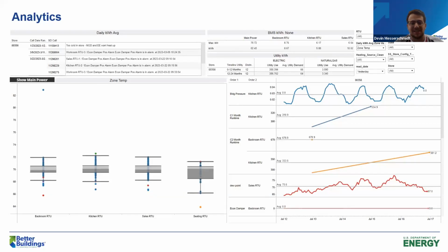Values for a specific site are found in the bottom right trends. We have different trends, from run times of heating and cooling to dew point to economizer position, anything we think is important. In the top left, you can see our current maintenance calls. If we're auditing a site, we don't want to send out a ticket for something that's already being worked on, so it's an extra check for us.